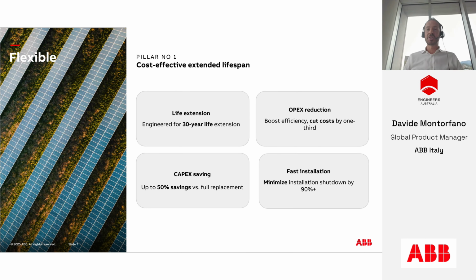Also, since you are not changing the medium voltage cable and the low voltage connection, you are also avoiding the typical unplanned cost that you have when you do the full switchgear replacement. We met customers doing the full switchgear replacement who, at the end, due to unplanned cost, civil works, and problems with the medium voltage cable, end up at 4 times the cost of the price of the switchgear. And definitely this is very painful for our customers. Having a cost not planned is definitely a problem.